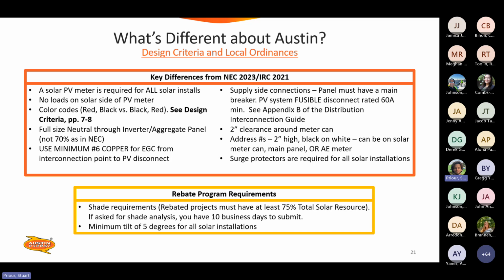So for some reason, even if you have a system that doesn't require a 60 amp disconnect, you'll still need to have an enclosure that's rated at 60 amps. You also need 2 inches of clearance around all meter cans. That will get rejected if you don't have it on all sides. You need the address numbers of the home to be 2 inches high, black on white, and they can be on any of those enclosures, the meter cans or the distribution enclosures.